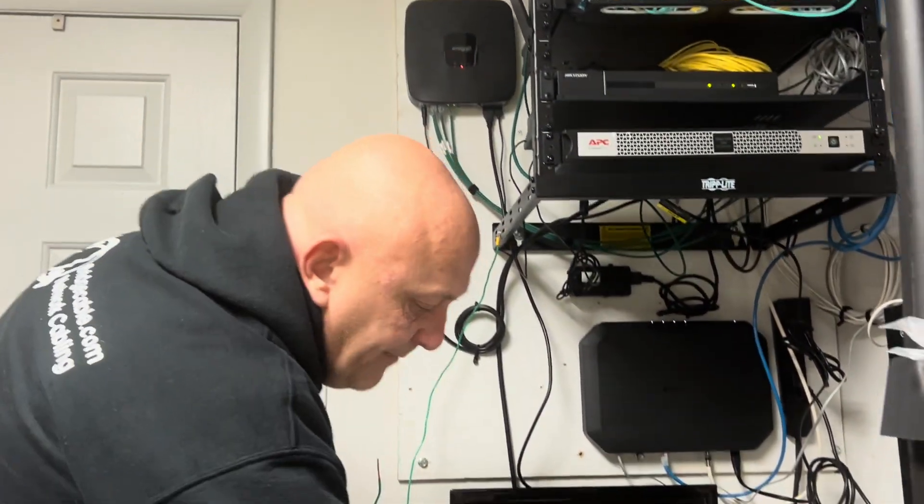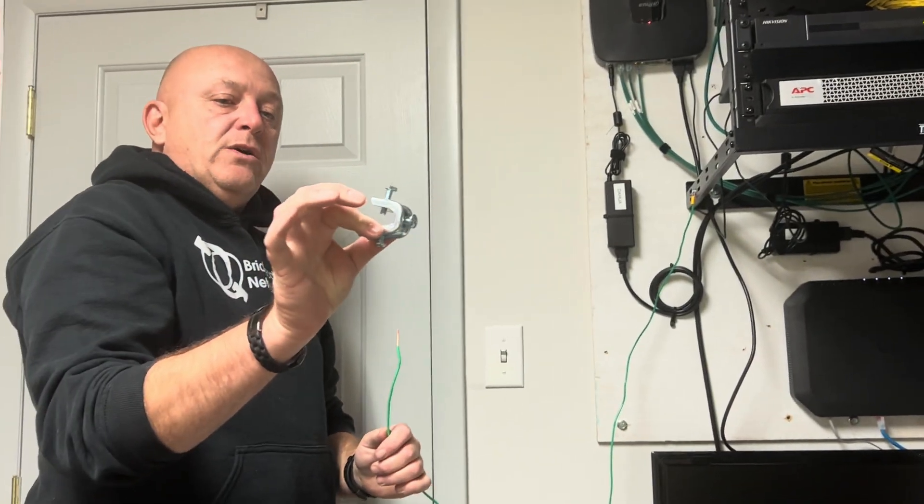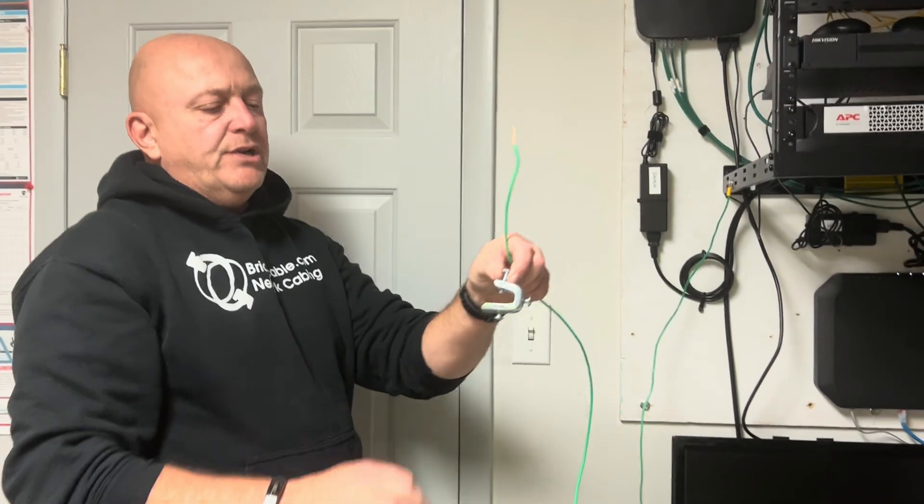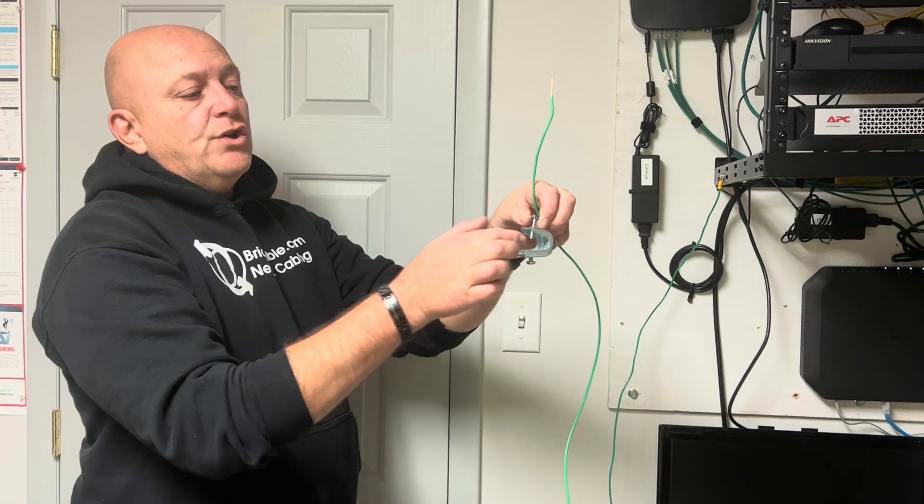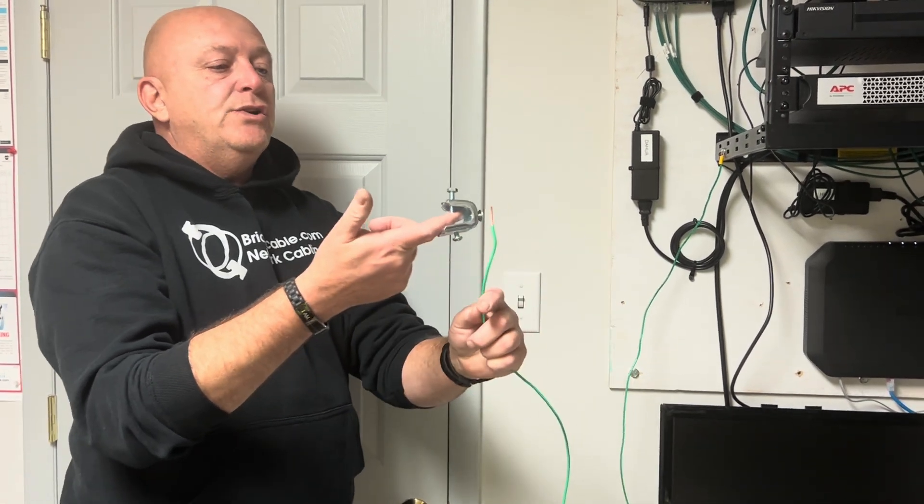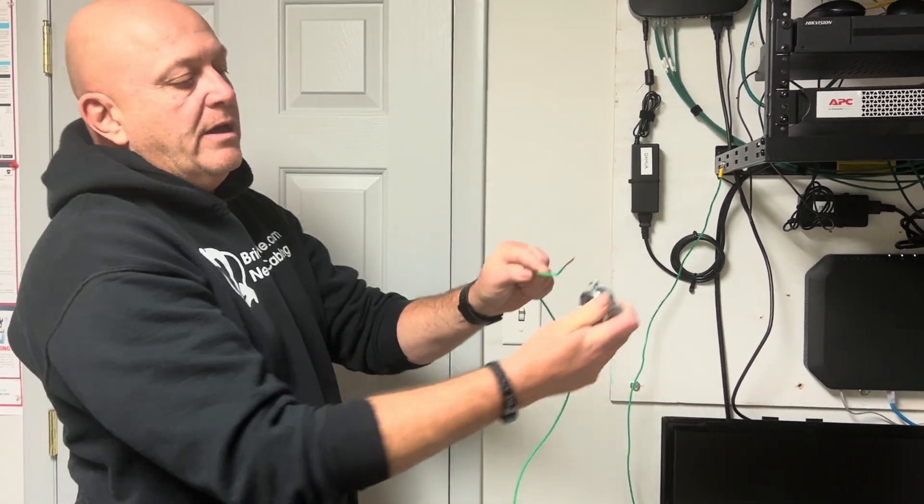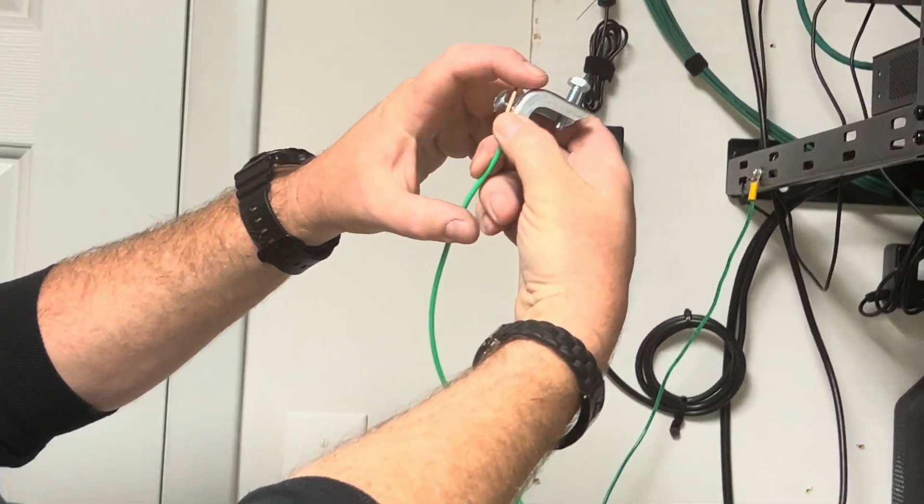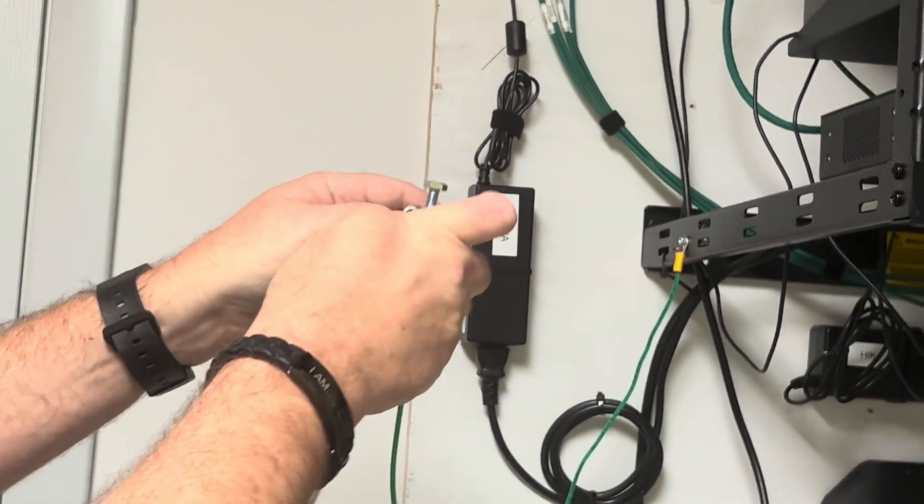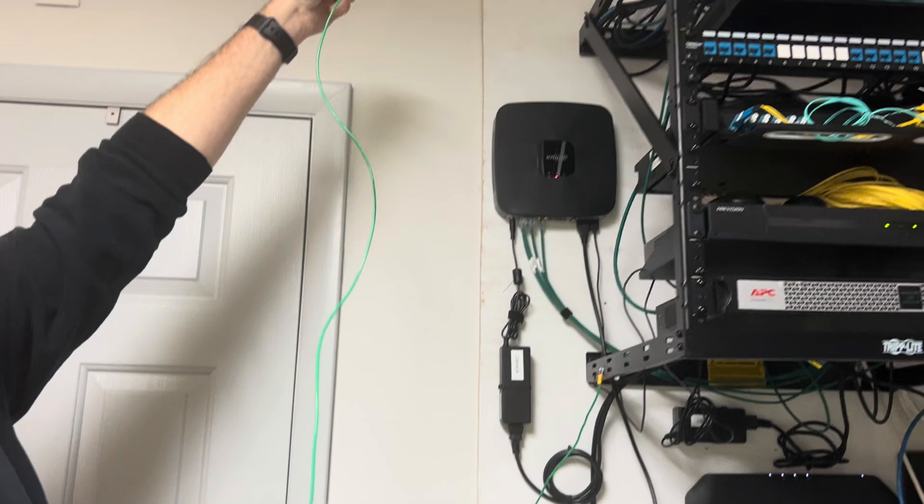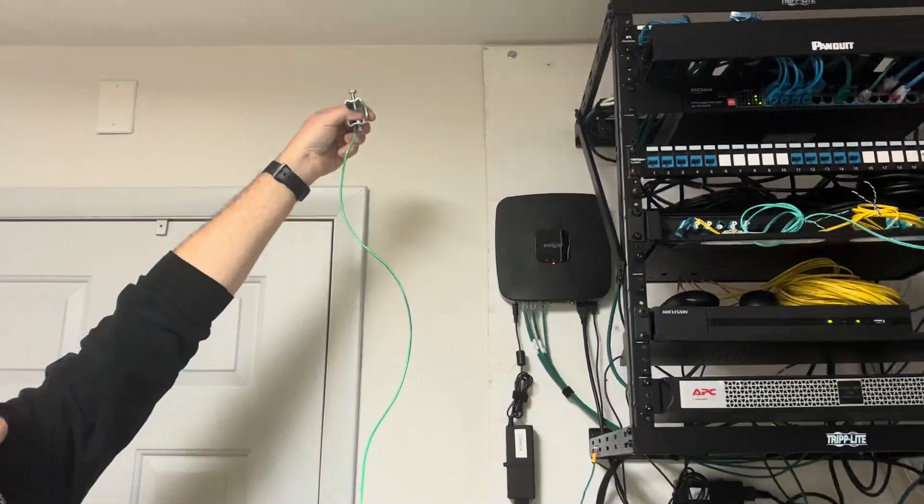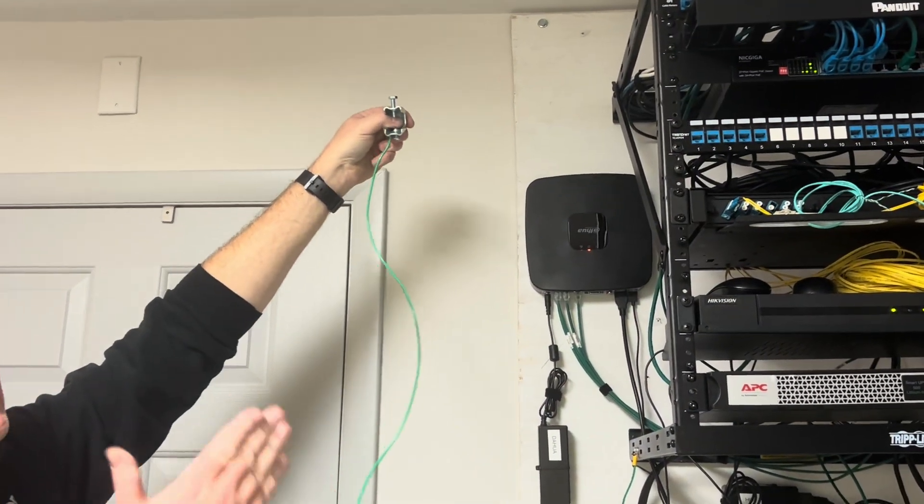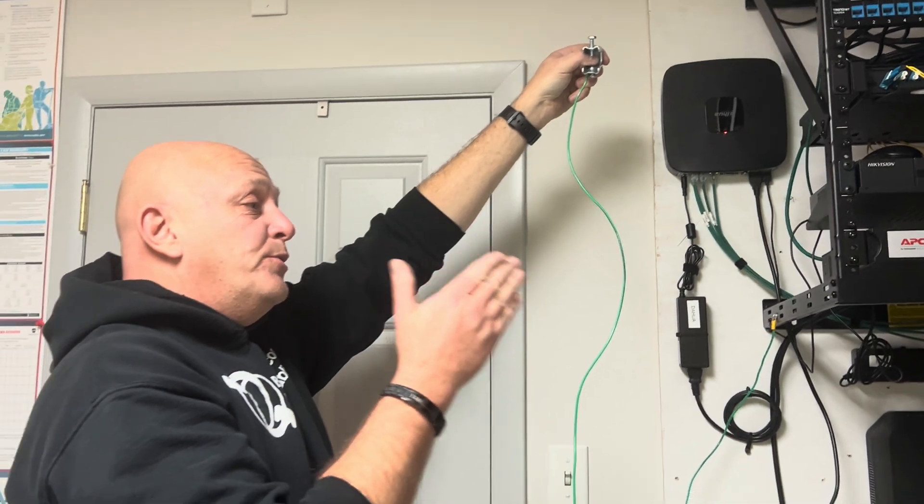How do you do that? Standard i-beam clamp. So you're going to screw it there and then you can put another eyelet on it and then you're just going to attach it on a quarter 20. So you have this way up in the ceiling on the metal which is supposed to be structurally grounded already and that is grounding on a budget.